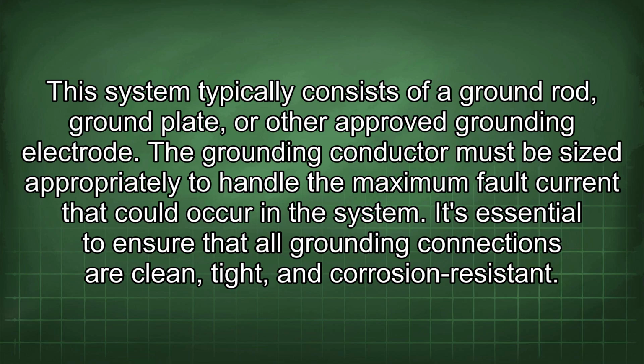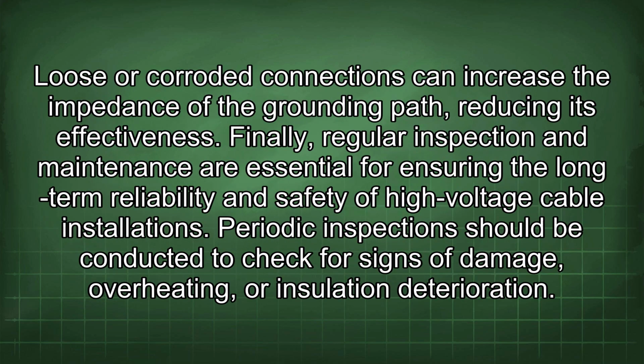It's essential to ensure that all grounding connections are clean, tight, and corrosion resistant. Loose or corroded connections can increase the impedance of the grounding path, reducing its effectiveness. Finally, regular inspection and maintenance are essential for ensuring the long-term reliability and safety of high-voltage cable installations.